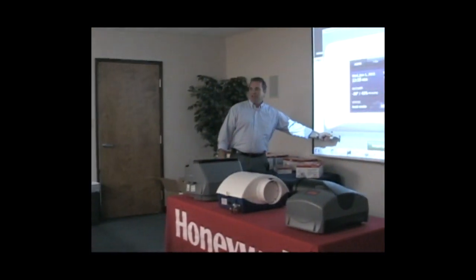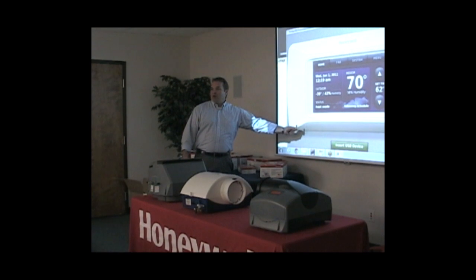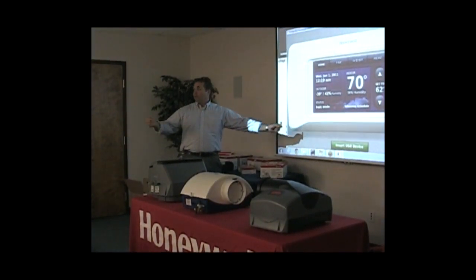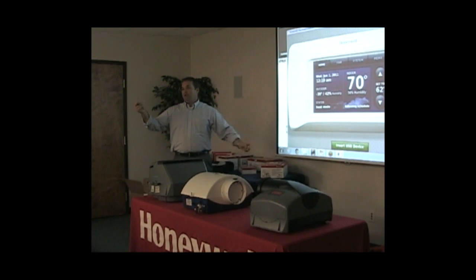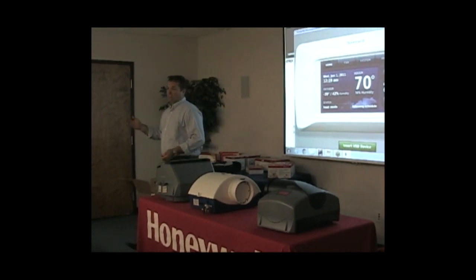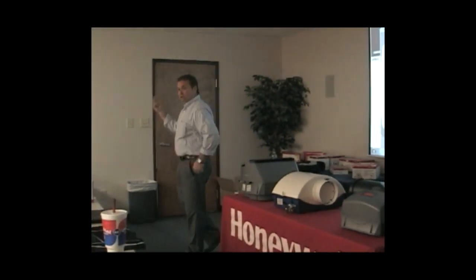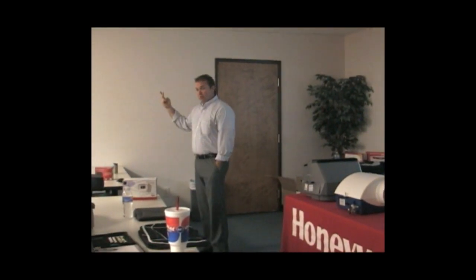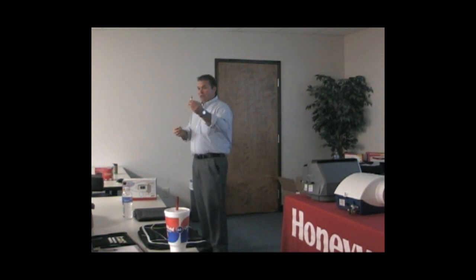But at the bottom of this thermostat is a USB stick. So if I put that in the bottom, and we just did a dual fuel - we just did a 2 heat, 2 cool dual fuel, which actually means it's 4 heat. I've got a 2-stage compressor, and then below 35 I go 2-stage gas valve. That's 4 stages of heat. I save all those setups and label my file - my 4 heat, 2 cool dual fuel file.